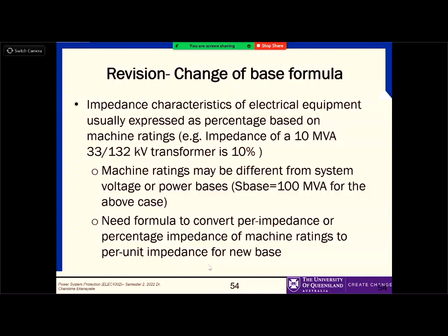Let's say, as an example, impedance is given for a 132 kV, 10 MVA system. How can I change it to a 132 kV, say 100 MVA system? Because at the end of the day, you have to change it to a constant power base.